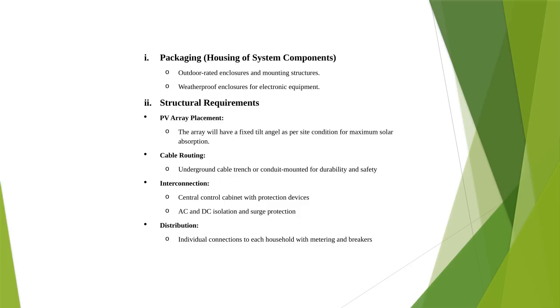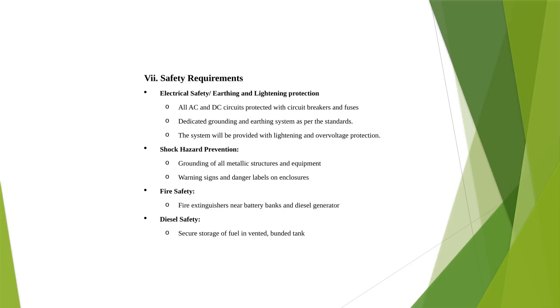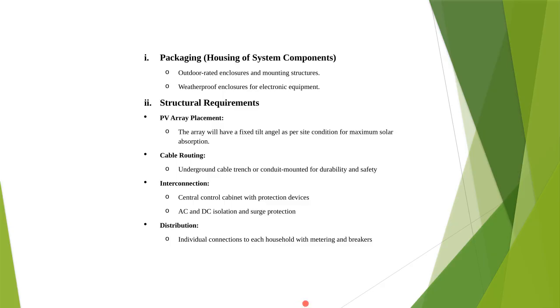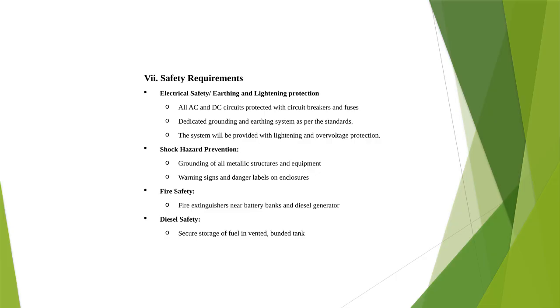Other interconnections will have a central control cabinet with some protection devices, as earlier alluded. For distribution, individual connections to each household with metering and breakers. Now, the safety requirements for the system: electrical safety, or earthing and lightning protection, with AC and DC circuits protected with circuit breakers and fuses. There will be a dedicated grounding and earthing system as per the standards. The system will also be provided with a lightning and over-voltage protection system.